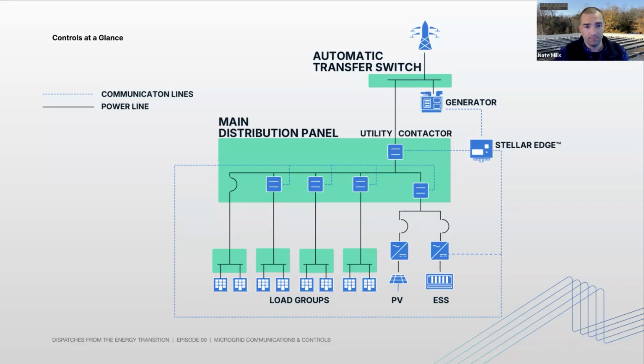That transition time, depending on the OEM of the battery itself, can take milliseconds, or it could take 10 to 15 seconds, just depending on what size range you're working in and who the manufacturer is. That transition from grid following to grid forming is also not necessarily controlled by the Stellar Edge. And so the point I'm trying to make here is that when we talk microgrid controls, there are multiple levels of control systems all throughout the system.